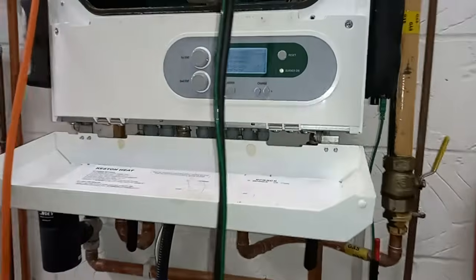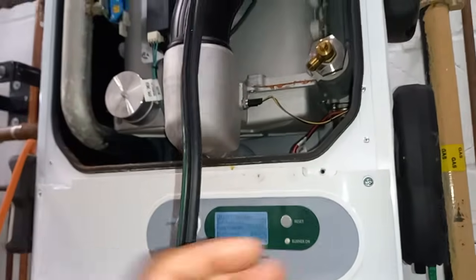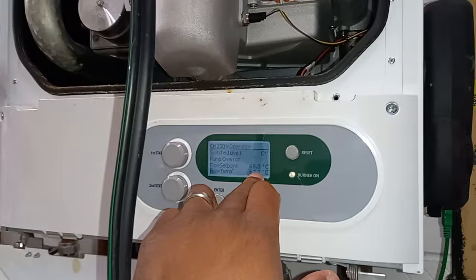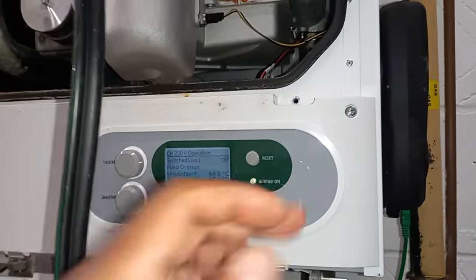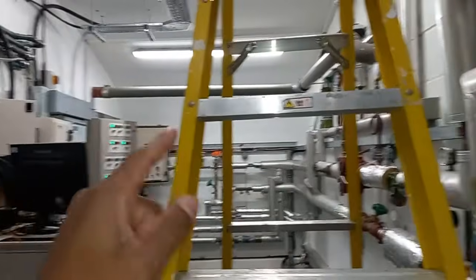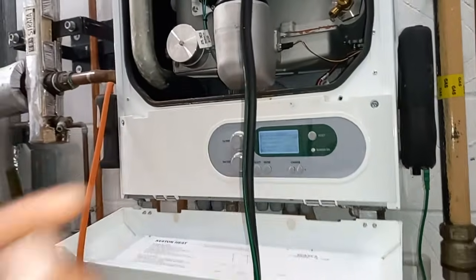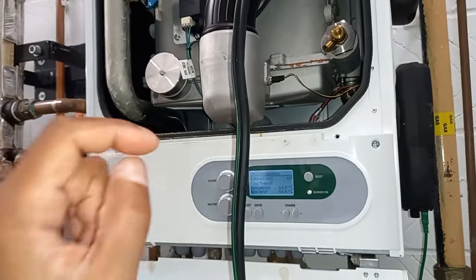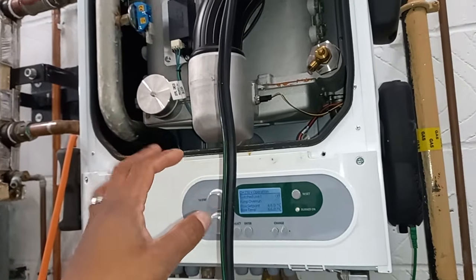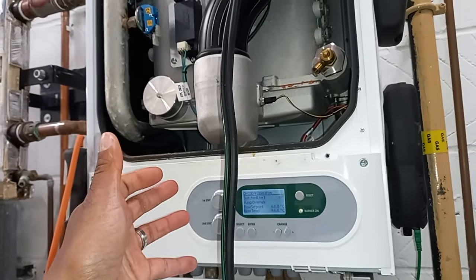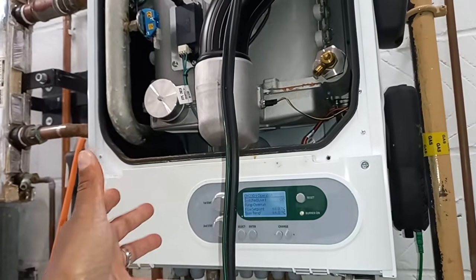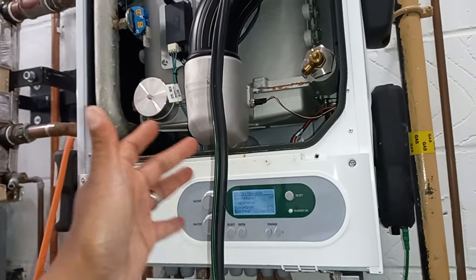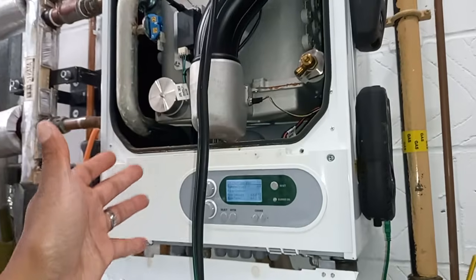Why am I turning my boilers off? Obviously because I don't want the heat to the boiler to get too hot. But later we're going to turn up our flow set point so that the boiler stays on for longer. So in this boiler here, you've probably got a switch live as well from that panel. It's more than likely a 0 to 10 volt signal for it to come on. Depending on the 0 to 10 volts, it will get the boiler to output 100%, or operate at a percentage based upon the voltage that you're receiving.